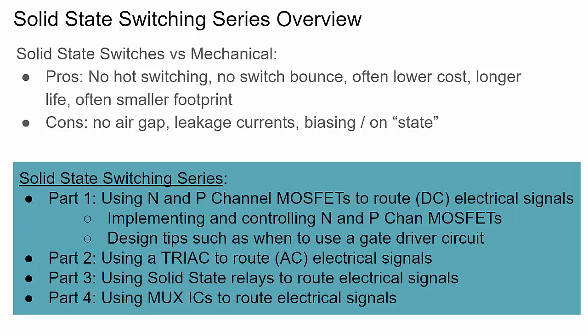The drawbacks to solid-state versus mechanical is there is no air gap. With mechanical relays you get air between your signal paths, and a lot of industries like that for safety reasons. Related to that, solid-state devices often have leakage currents because you don't have that air gap — there is a small amount of current flow, but it'll be very minimal. Biasing to an on or off-state can also be a little more complex.